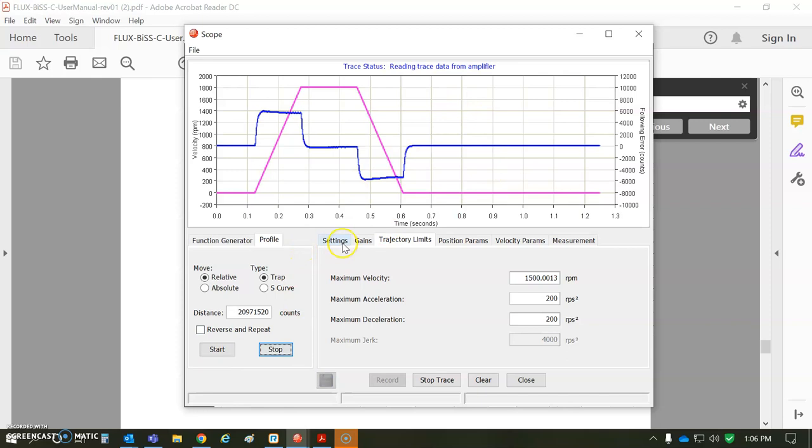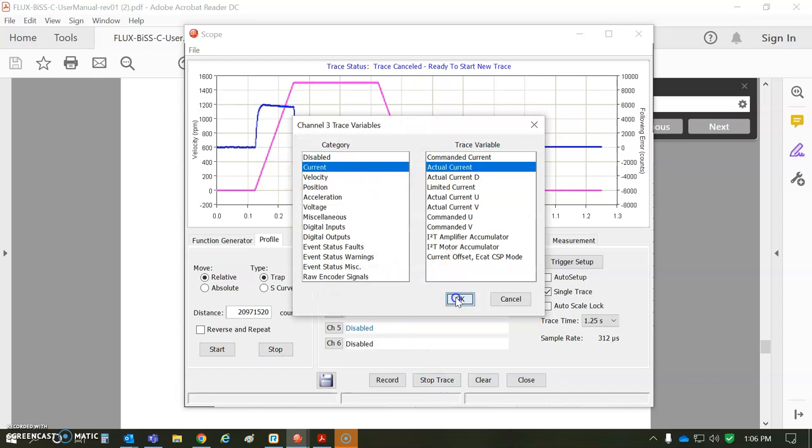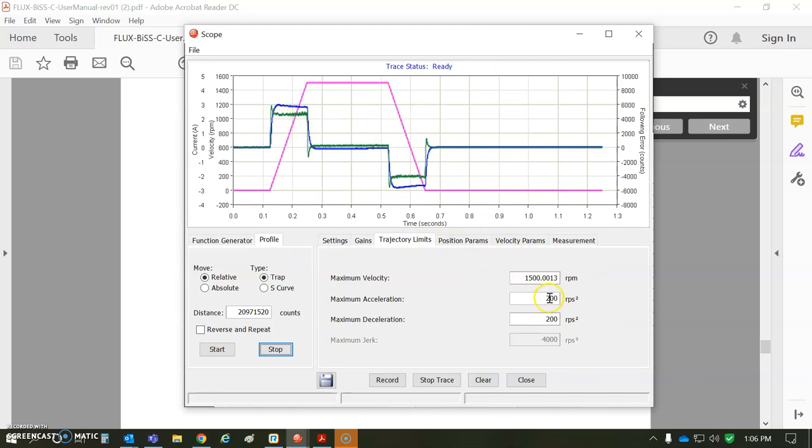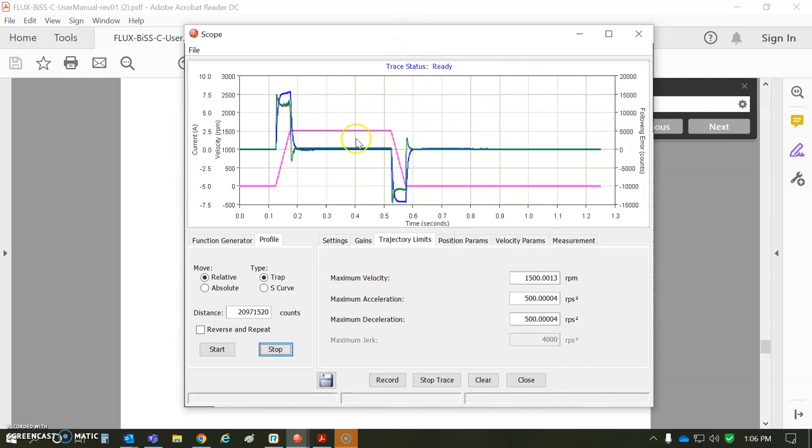Let's take a peek at the current. We'll do current actual commanded current. This is just with the motor inertia, whatever that is, and you'll see some peak current required. That's like a couple of two, three amps. We can crank this up. This will consume a little bit more peak current. I think this drive would do 15, the motor's like 13. Yeah, we could have 50 revs per second per second. We can easily do 10 times the inertia and not even consume the motor's rated current. And then the move and settle still looks pretty darn good there.